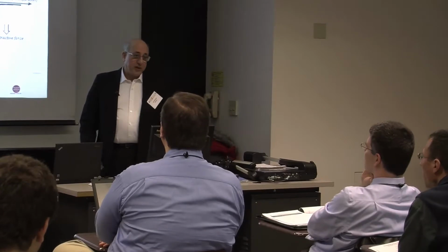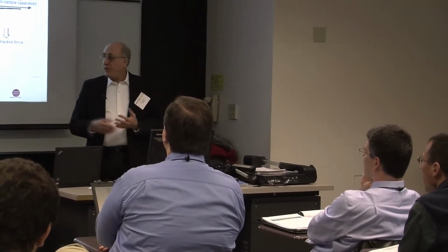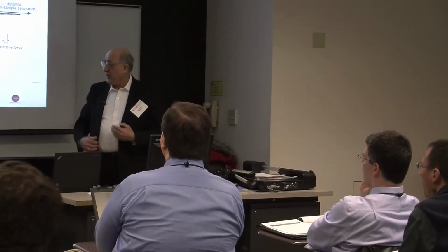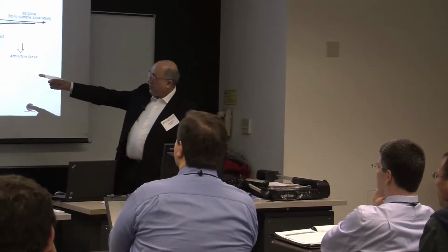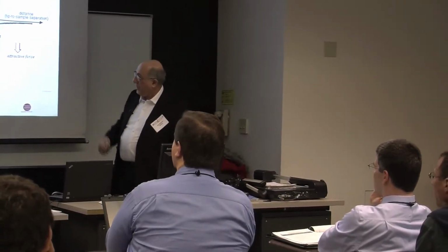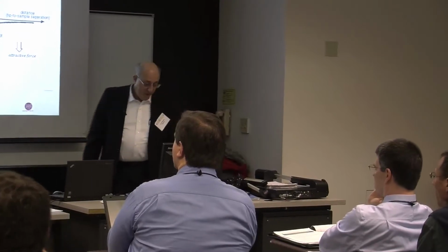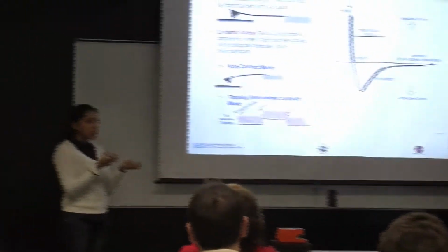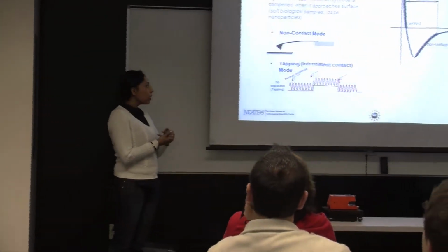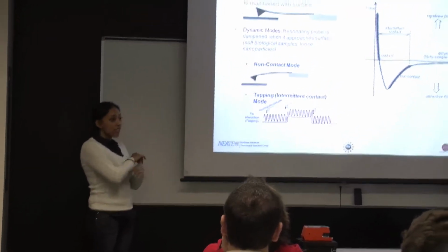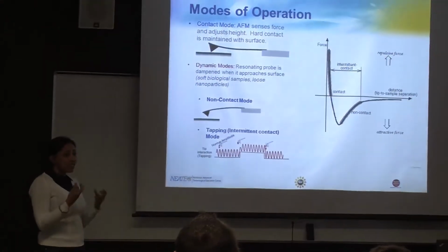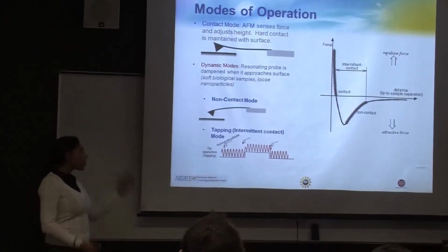Sometimes you want to have contact. For example, for solids, we use contact mode, as long as you don't destroy the sample or the tip. But probably this is the best way to do it. For biological samples, and for new samples like nanoparticles and such, the contact tip can actually slice through DNA, it's that hard. So for that, you want something else. Yeah, it will interfere with the sample.